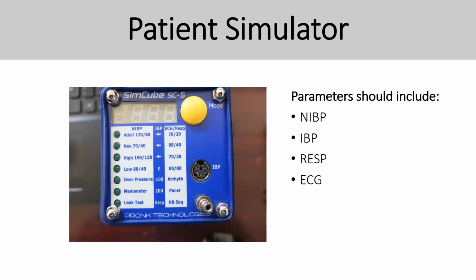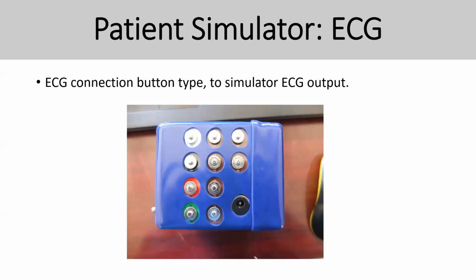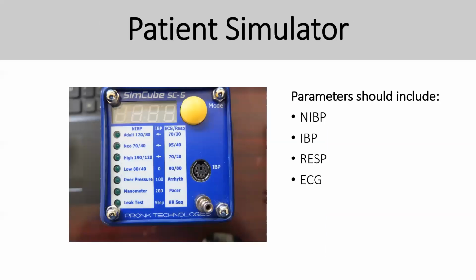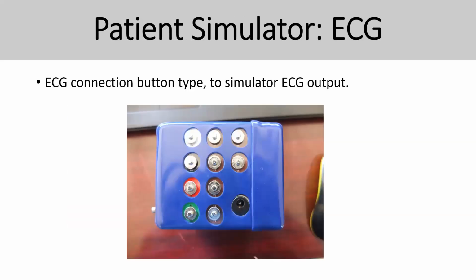So patient monitors normally always have ECG, respiratory, NIBP, and IBP. By using this patient simulator, you can measure NIBP. These are SimCube units, so you can measure NIBP. For IBP, you need to have a special connector. Respiratory and ECG work together. Basically, when you run the ECG, respiratory will work together, that's how the reading is set up. So when you set ECG to 70, the respiratory will be 20.